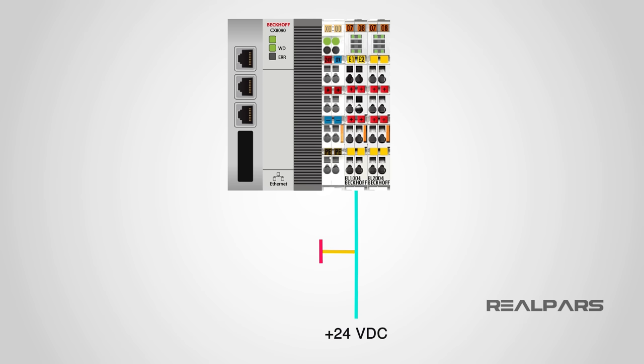With this normally closed switch in the normal state, there is a 24-volt signal connected to the PLC input, giving an emergency stop healthy signal to the PLC or other safety systems. When the switch is pressed, the healthy signal will be lost, and that's how the PLC or safety system knows to shut down the whole system, right?